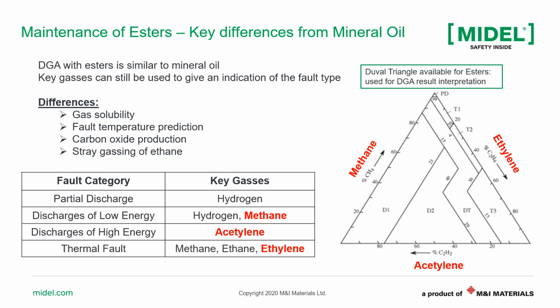You see in the table here, for esters and mineral oil, a fault category such as partial discharge can be indicated by hydrogen. Now if you have hydrogen and methane, that can indicate discharges of low energy. If you have acetylene, that always indicates discharges of high energy. And then finally, if you have methane, ethane, ethylene, you can indicate a thermal fault. On the right-hand side of this slide, you can see the Duval triangle, and I'm sure a lot of you are familiar with it. We do have Duval triangles for esters equivalent to that of mineral oil. We just need to use the right one when we interpret.